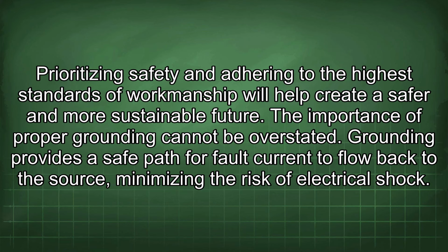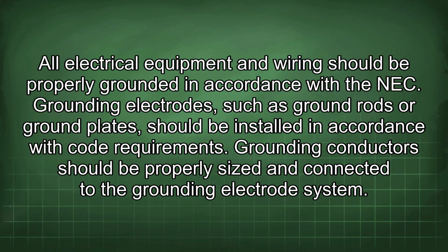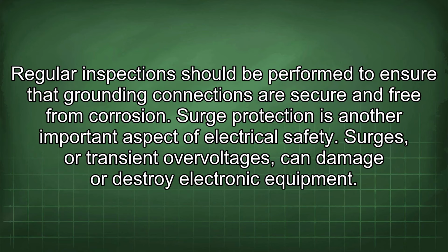Grounding provides a safe path for fault current to flow back to the source, minimizing the risk of electrical shock. All electrical equipment and wiring should be properly grounded in accordance with the NEC. Grounding electrodes, such as ground rods or ground plates, should be installed in accordance with code requirements. Grounding conductors should be properly sized and connected to the grounding electrode system. Regular inspections should be performed to ensure that grounding connections are secure and free from corrosion.